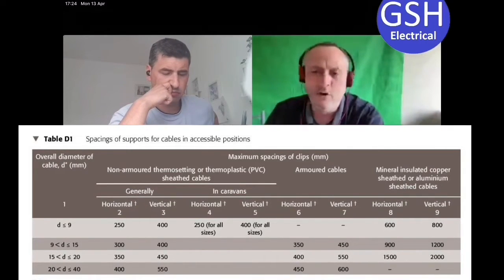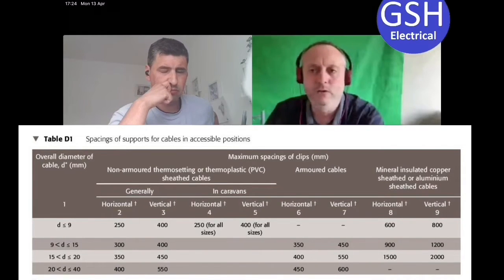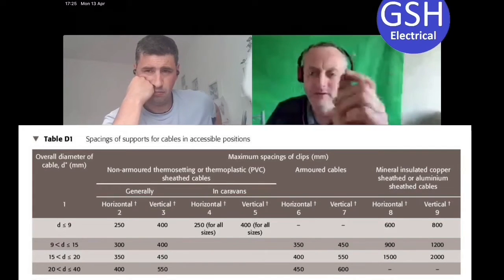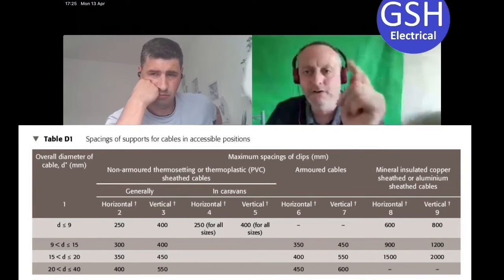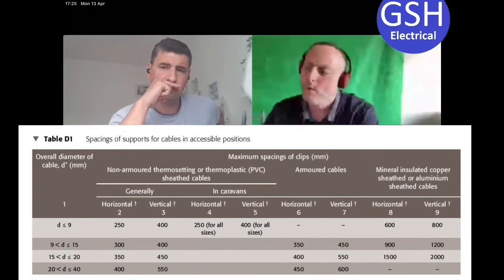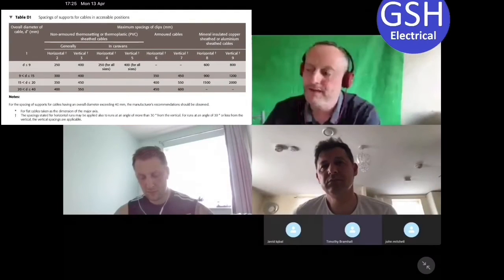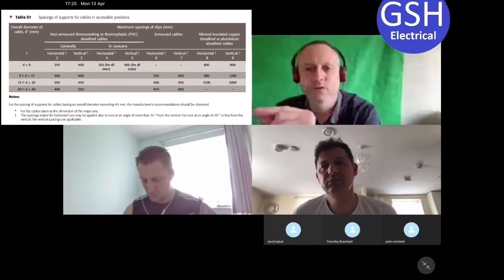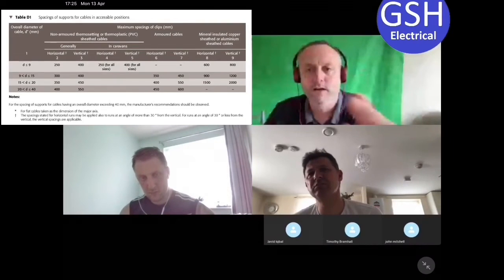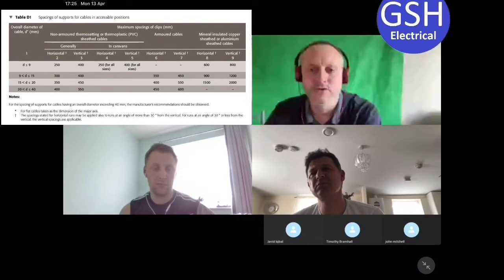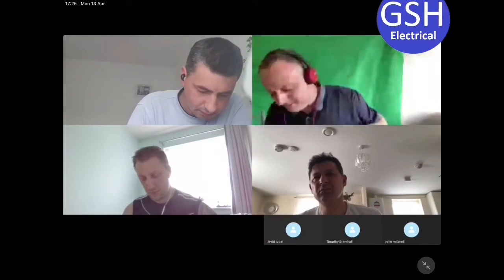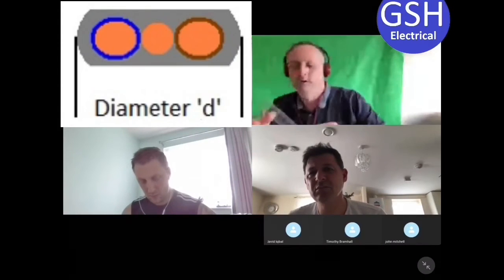In the workshop I normally say 300mm as a rule of thumb, because we've got all different cable diameters. So no greater than 300mm. We've got two maximums here: 250mm horizontally and 400mm vertically. So when you're installing systems or during on-site visits, don't clip cables that don't comply with what's in the table.